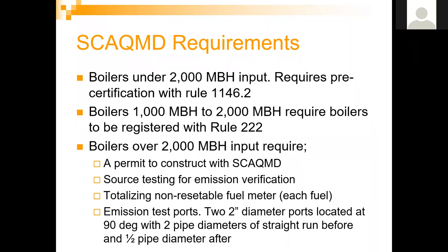Boilers in South Coast AQMD under 2,000 MBH input require what's called a pre-certification with Rule 1146.2. That means sending the boiler to an approved testing lab, running tests per air district requirements, and submitting those tests to have the boiler pre-certified. An entire series of boilers can be pre-certified. Currently, the rules for under 2,000 MBH are sub-20 PPM NOx and sub-400 PPM CO.